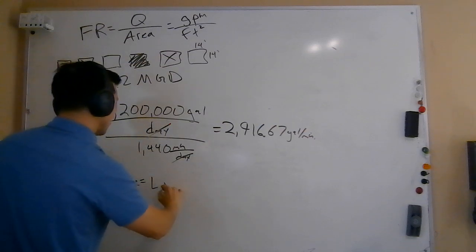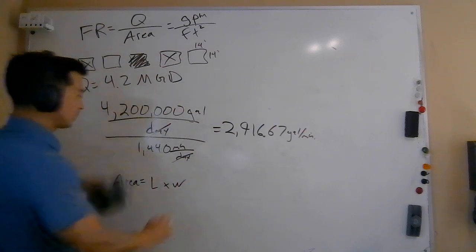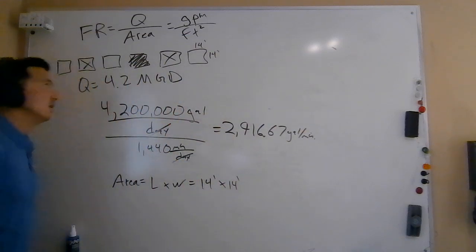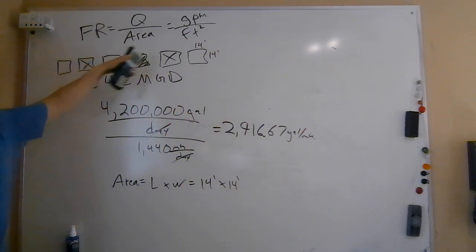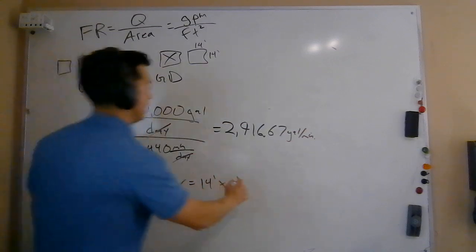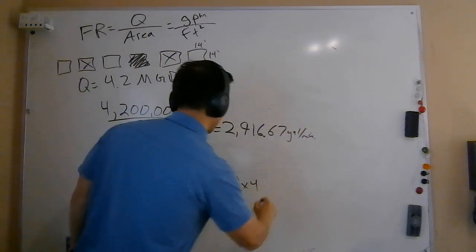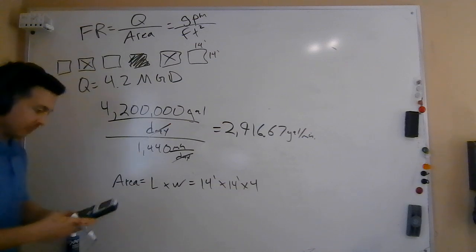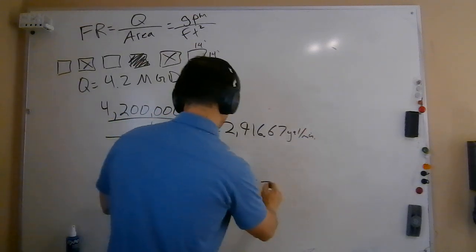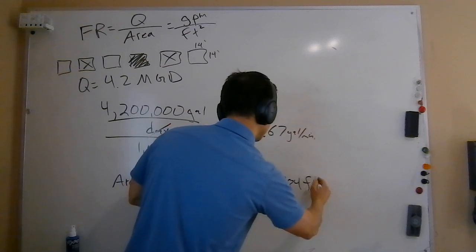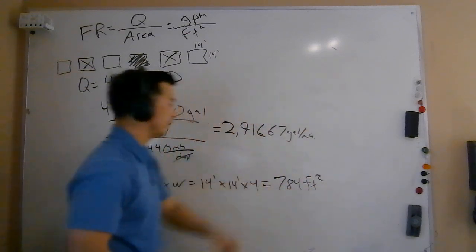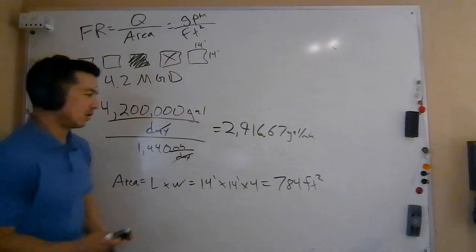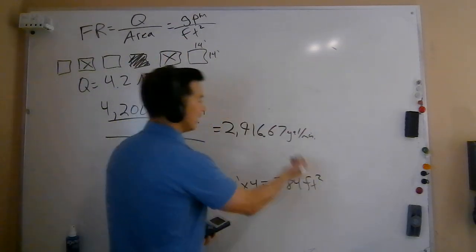So how do we calculate that? Well, it's just length times width. So in this problem here, it's going to be 14 feet times 14 feet. We also want to make sure we account for the fact that there are four filters treating this flow rate. So we're also going to multiply that by four. So what do I get? 14 times 14 times four filters. I get an area of 784 square feet. Remember square feet, feet times feet. Square feet makes sense because we're looking for an area.